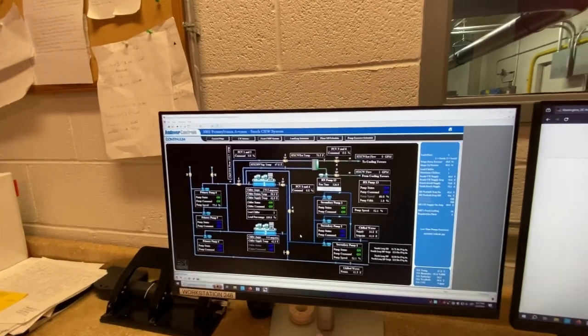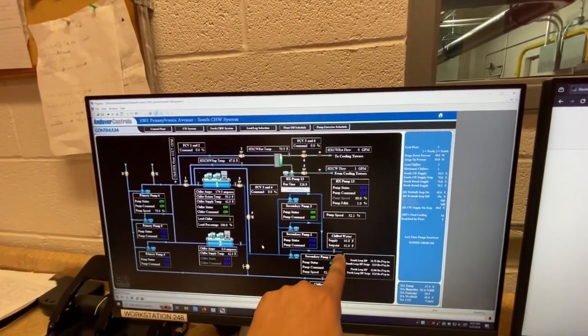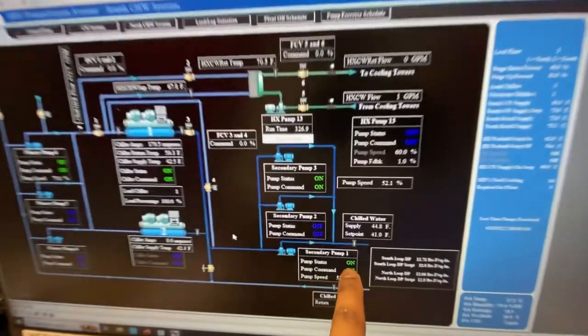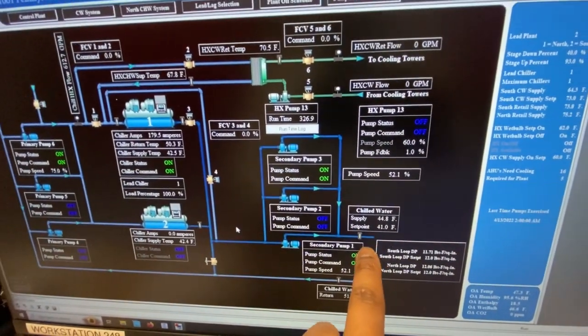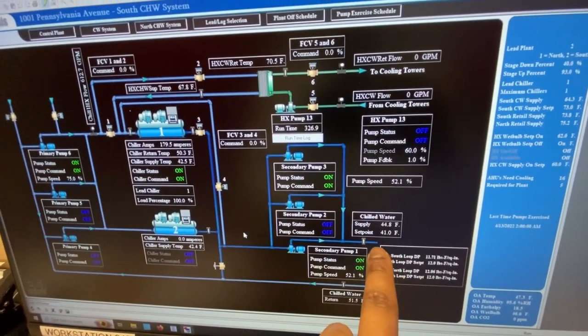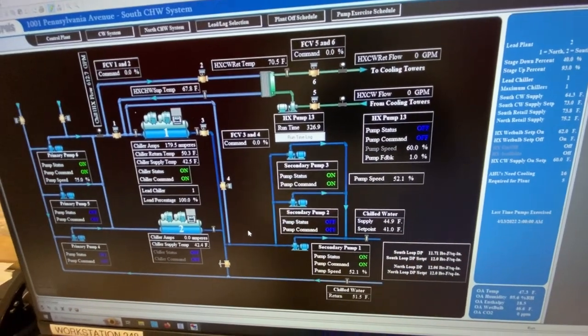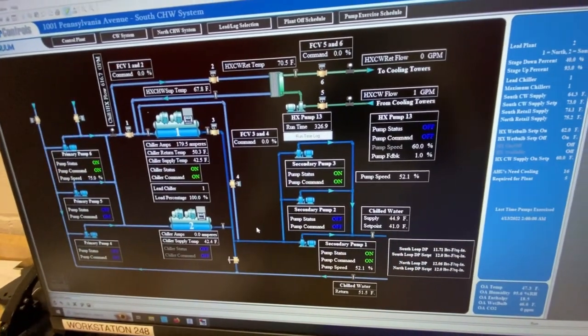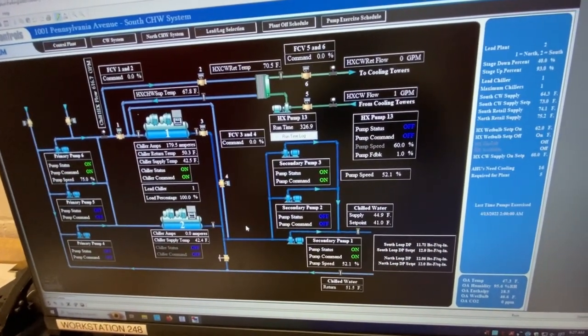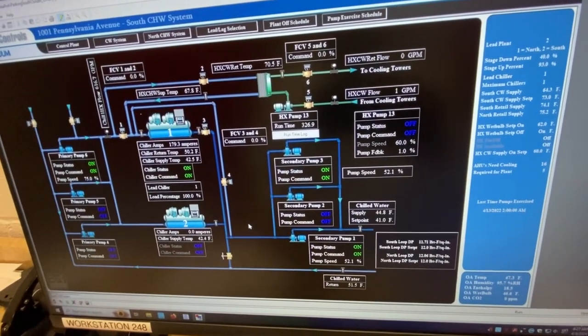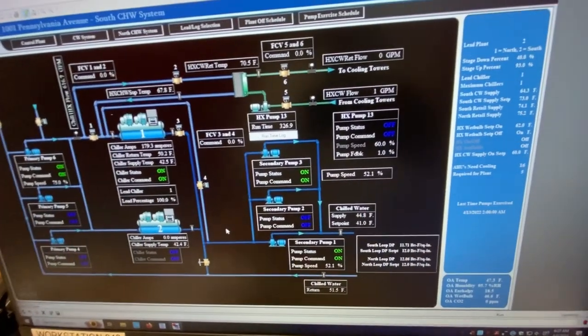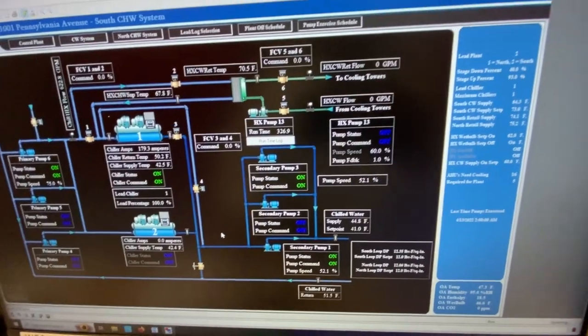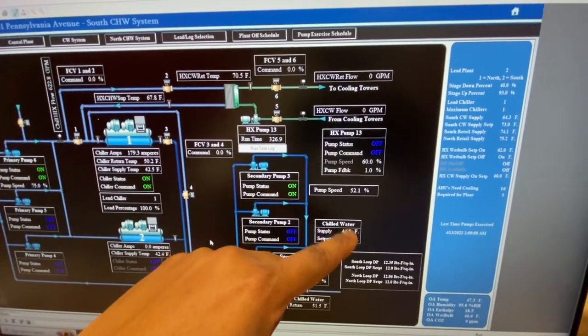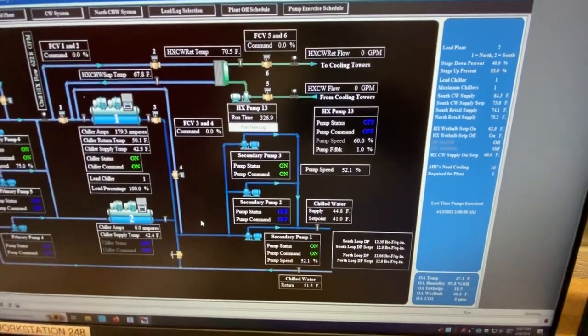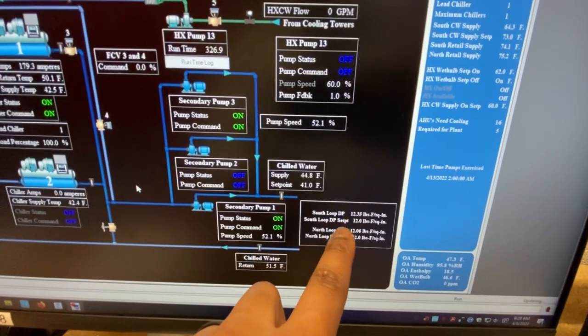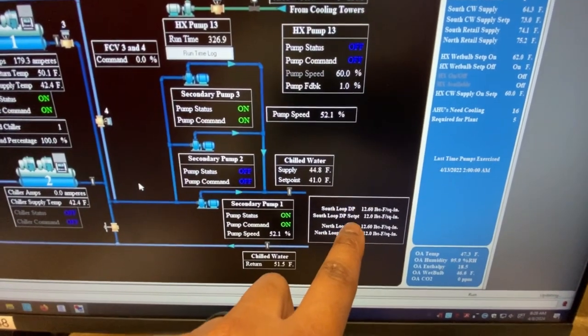My main target today: I don't want this number—right now the set point is 41—to start deviating towards 58, 59, 60. If it does, I'm losing the building, meaning I'd be supplying chilled water at 59 or 60 degrees, which is not good, especially on a warm day like this. I want my water temperature to stay around the 40s. That's my main focus right now. This is the DP right now, and the set point is 12.0.